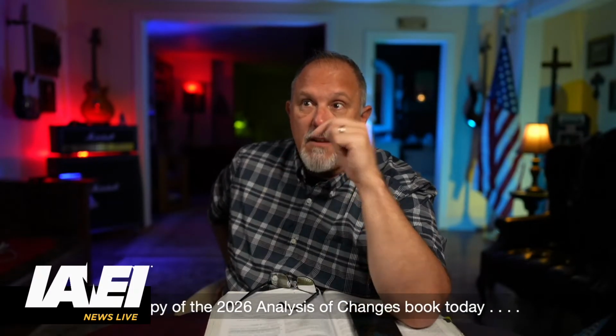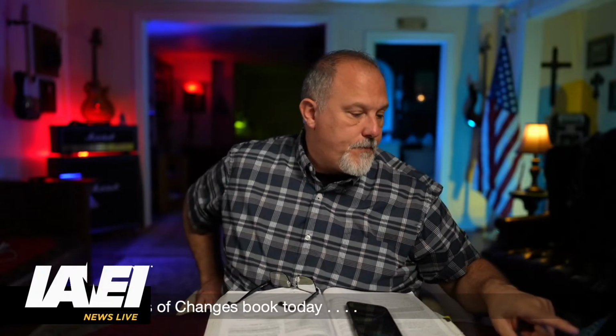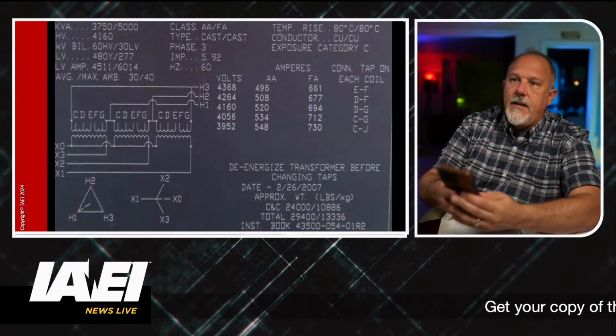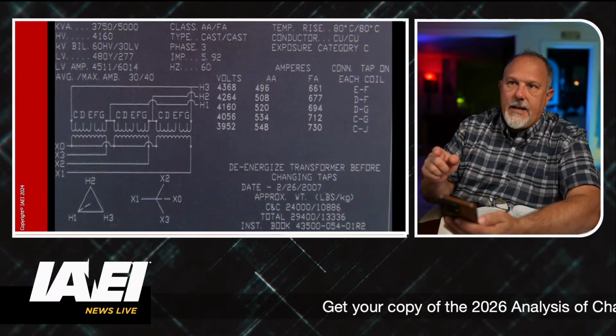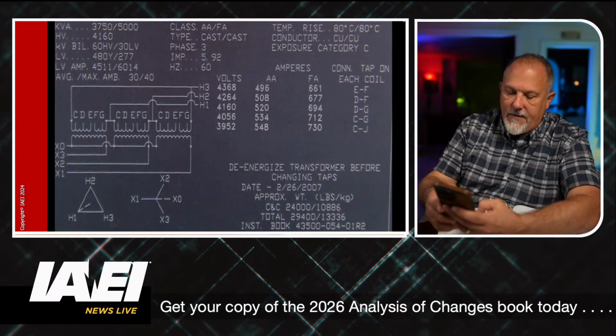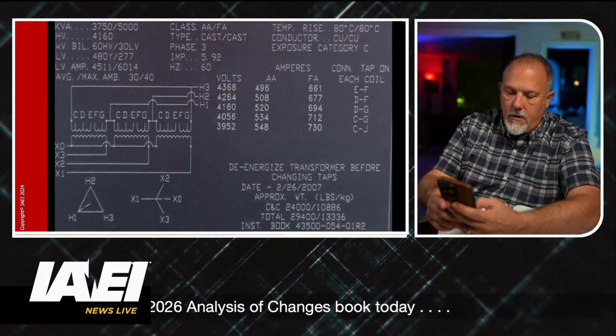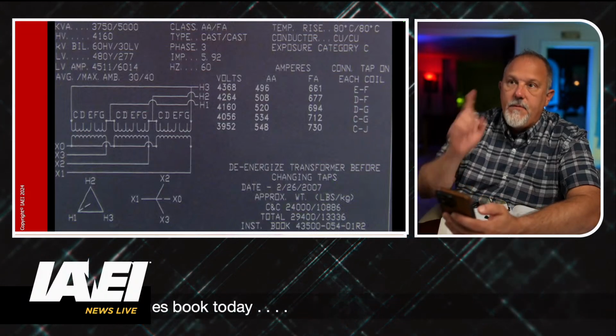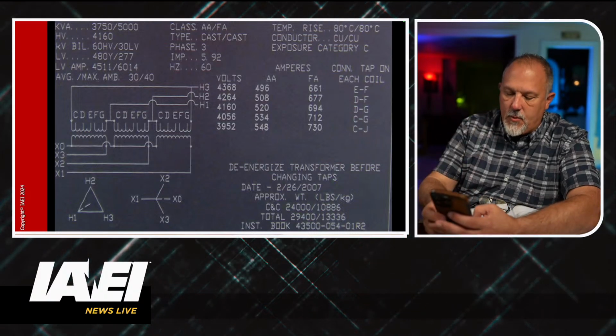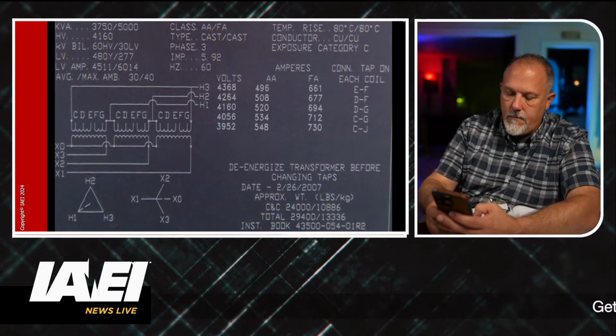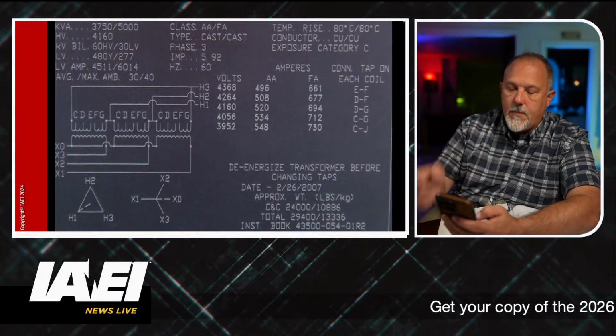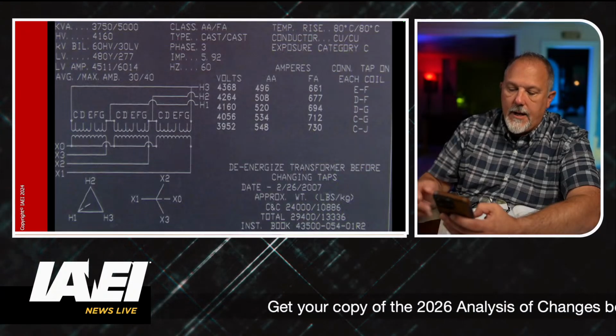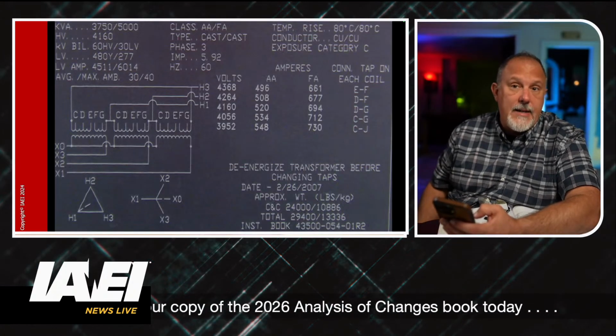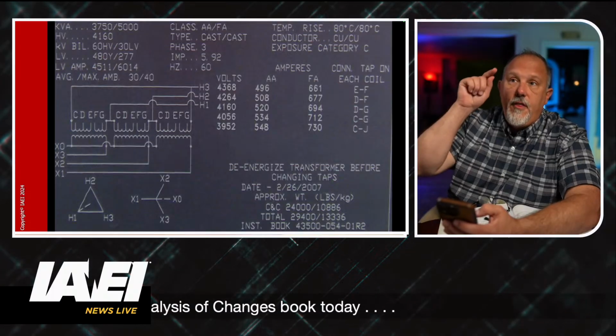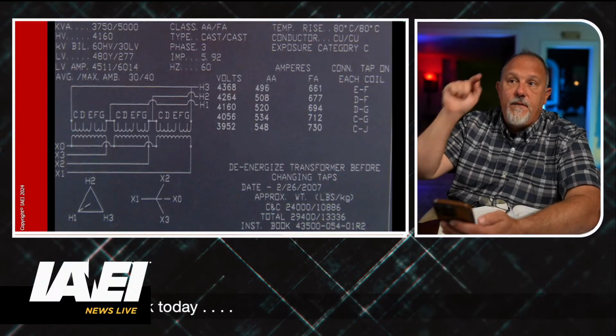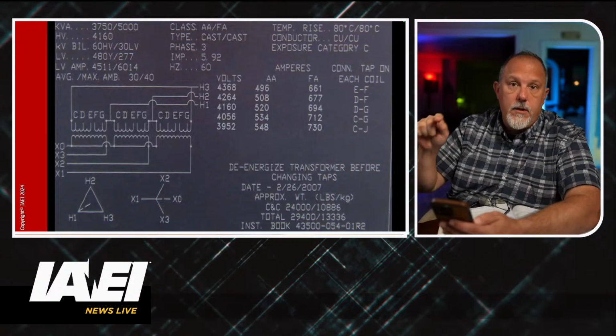So when I think about the fault current on this transformer, I'm going to take the full load amps on the secondary, which is 4511, divide that by 5.92, multiply that times 100, and I get 76,199 amps. So I would not base it upon the full load amps of 6014.